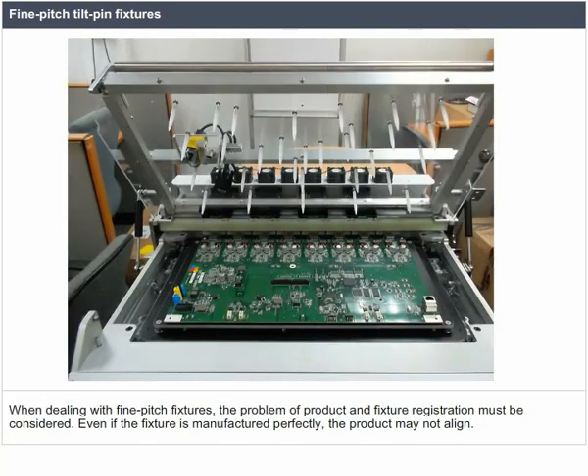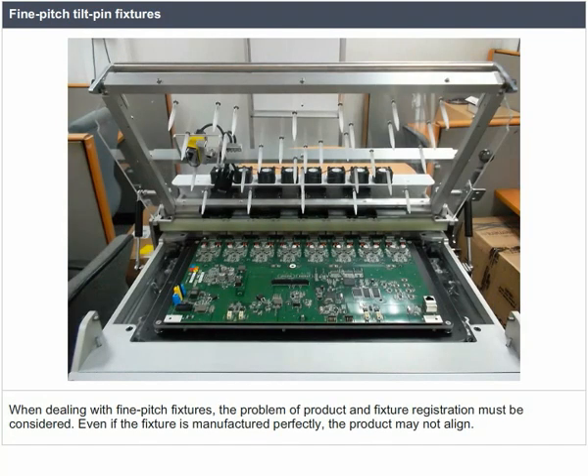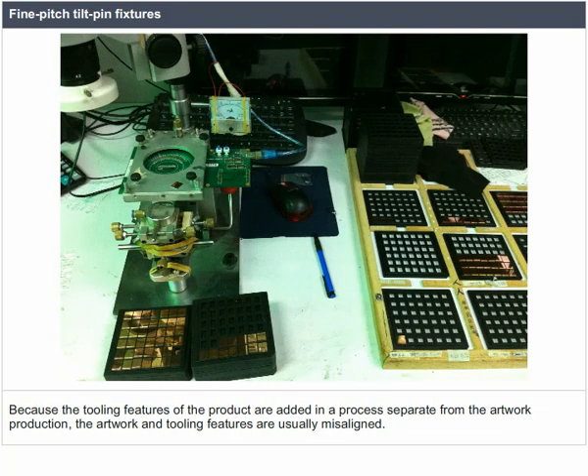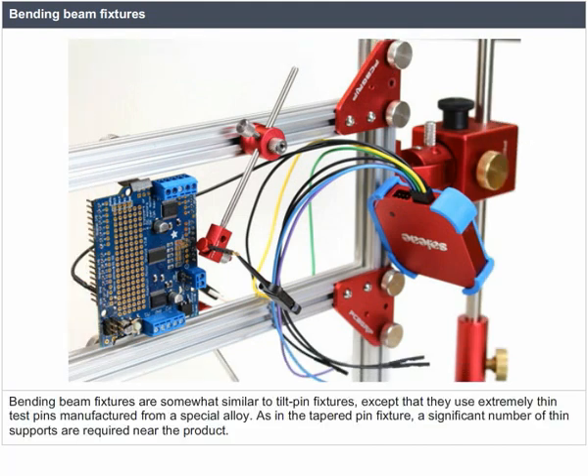When dealing with fine pitch fixtures, the problem of product and fixture registration must be considered. Even if the fixture is manufactured perfectly, the product may not align. Because the tooling features of the product are added in a process separate from the artwork production, the artwork and tooling features are usually misaligned. Bending beam fixtures. Bending beam fixtures are somewhat similar to tilt pin fixtures, except that they use extremely thin test pins manufactured from a special alloy.